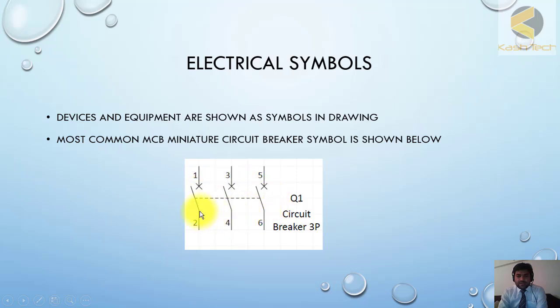When it is shown on the drawing, it is shown schematically like this. This is the way you represent a breaker. You can see here a cross symbol is used for the breaker, showing that this circuit can break the current. There are three poles - we can say red, yellow, blue - and these are the terminal numbers: one, three, five, two, four, six.